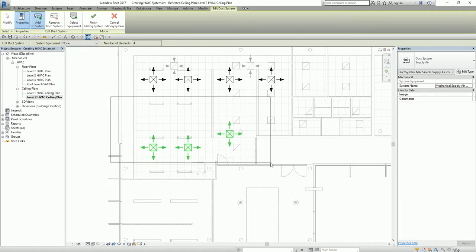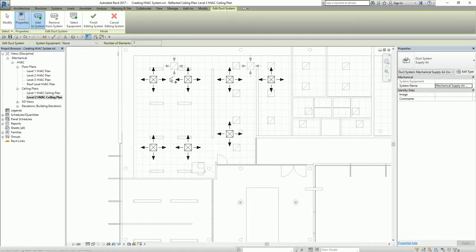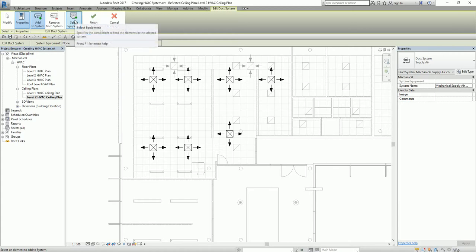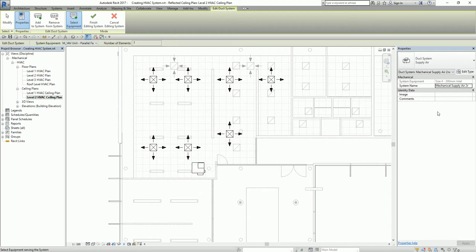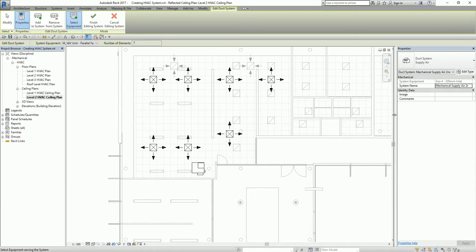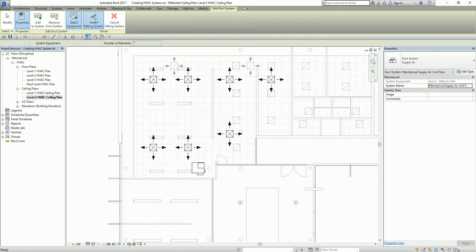I select all the supply diffusers — you can also use window selection. The total number of elements is seven. Then I select Select Equipment and choose the equipment I want to use to supply those air terminals. You can see this is now the system name. After selecting all the elements, I select Finish Editing System.